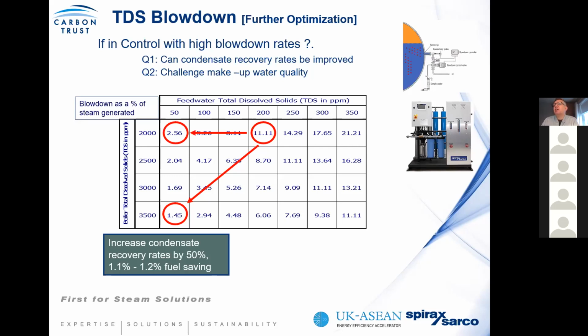However, if you were looking at increasing the blowdown rate, so for example, that your system is out of control and it's acceptable to go to 3,500 ppm or 5,000 microsiemens, simply bringing your process back in control means you can go from 11% blowdown rate to 6% blowdown rate at 3,500 ppm. However, if you start looking at changing the feed water quality, say RO water, for example, where instead of 200 ppm you're at 50 ppm, you will go from 11% blowdown rate to 2.5% at 2,000 microsiemens, or just under 1.5%.